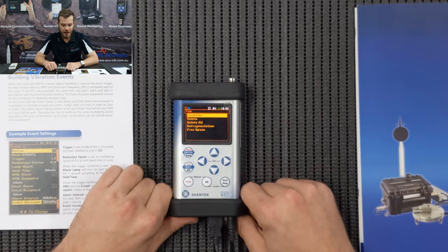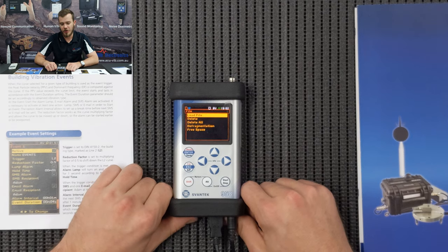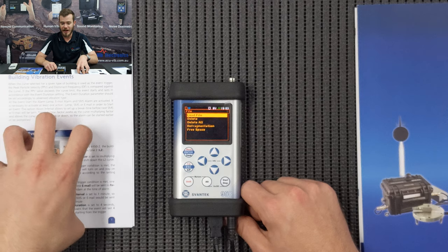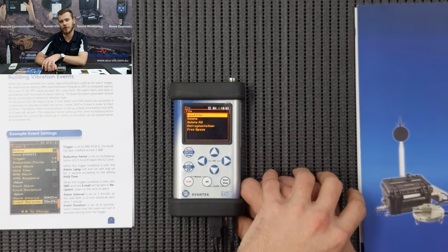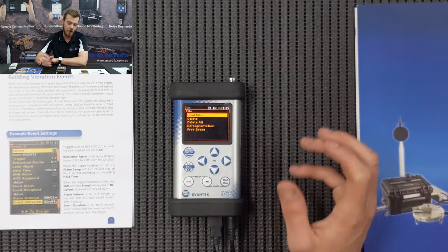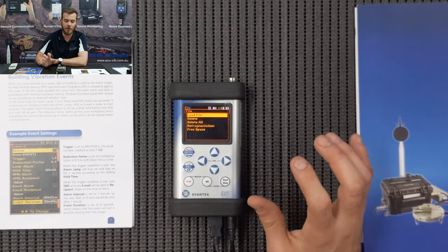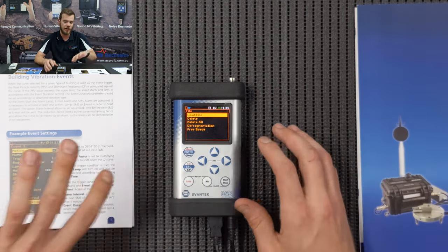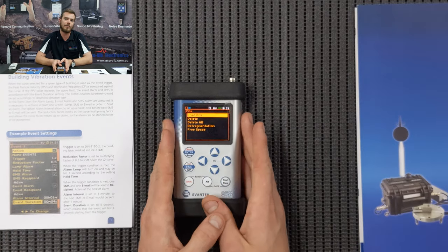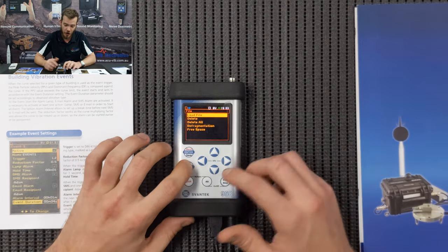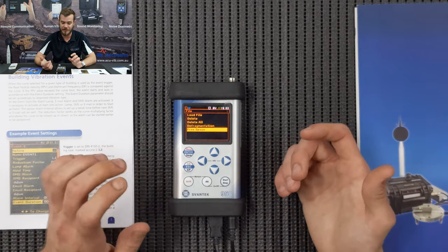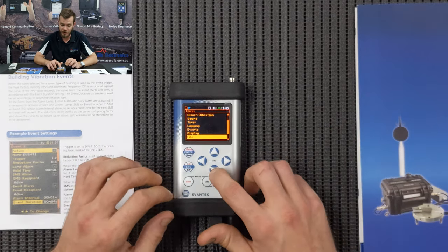So in the Svan, we have 30 megabytes of internal memory. We are using 15 megabytes for wave data, and we're using 15 megabytes for time history, and that'll also incorporate our summary results into that one file. So a little bit of a different file structure if you're using the instrument in ground vibration previously. Now we have load files, delete all, defragmentation and free space. These are all pretty self-explanatory. I'm just going to press escape.